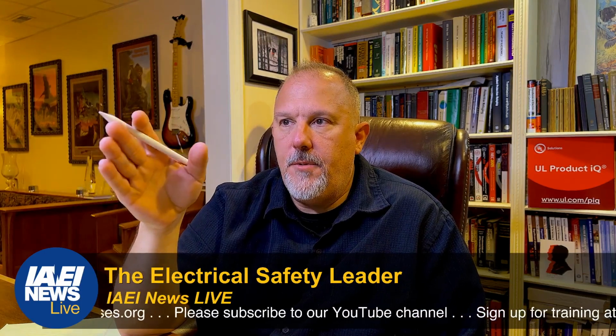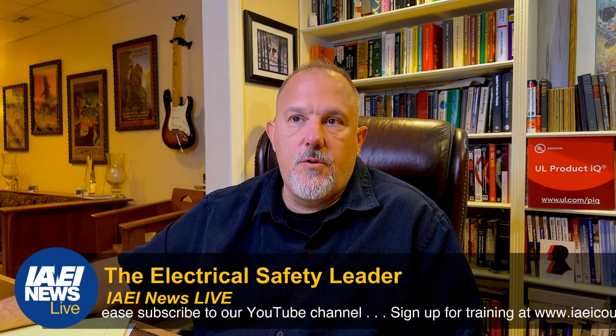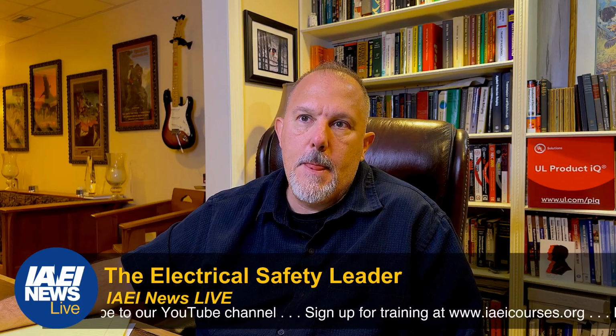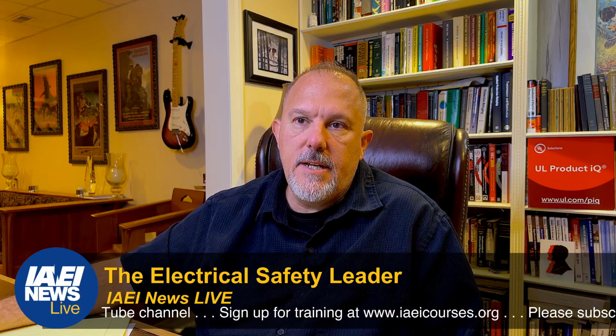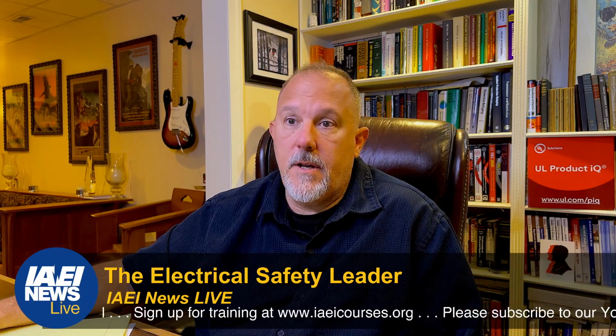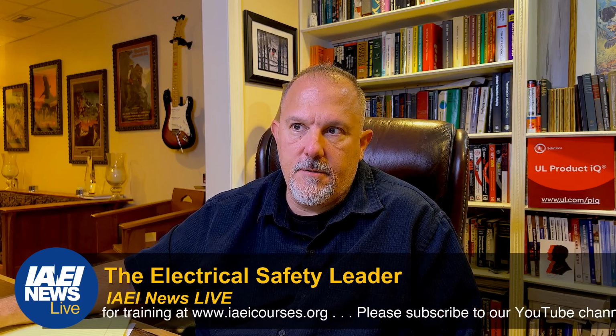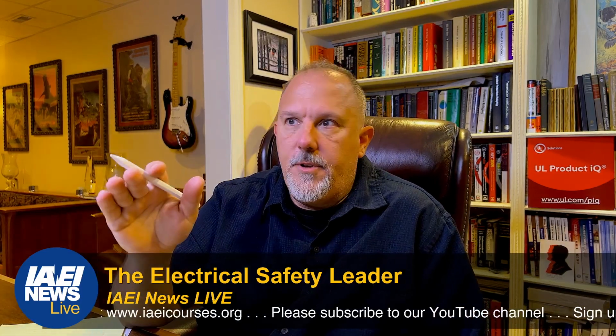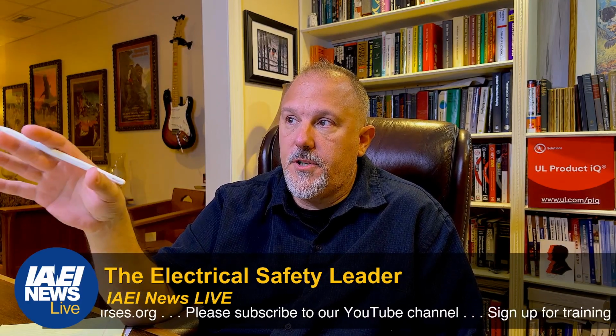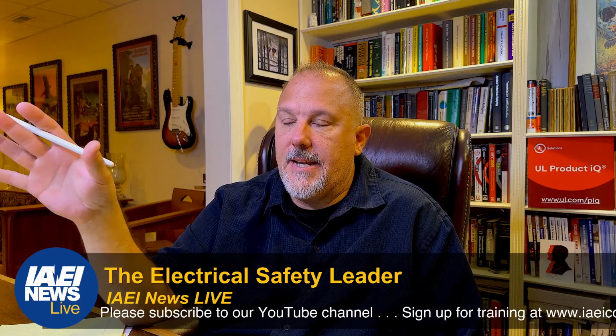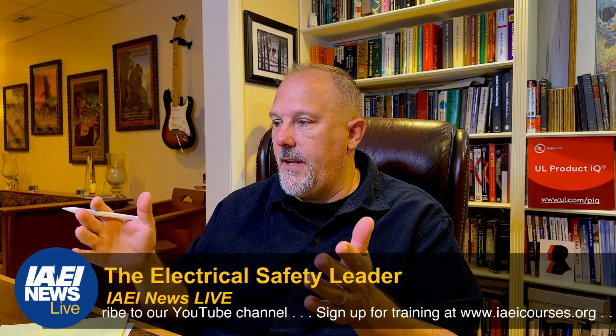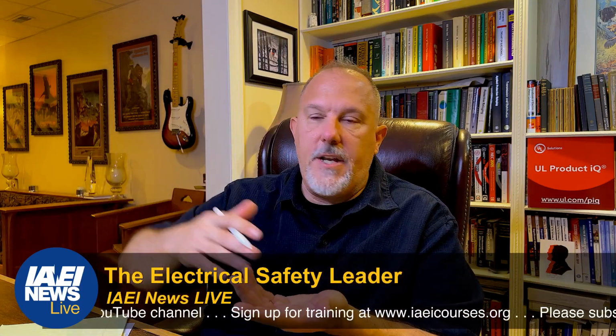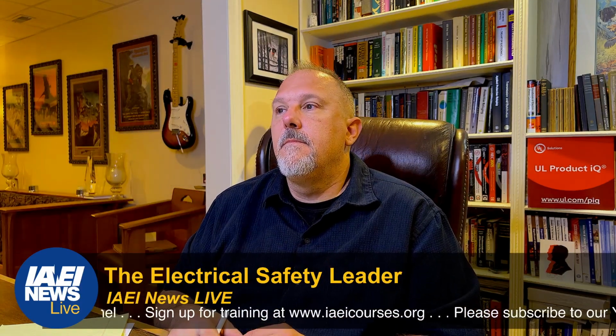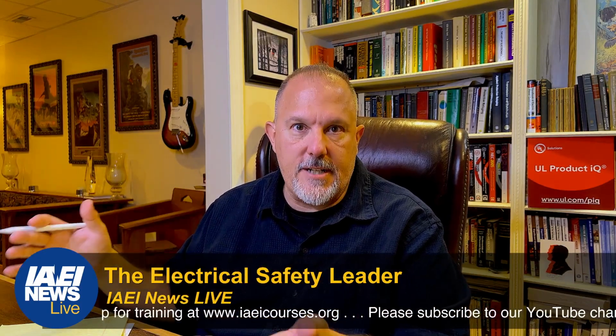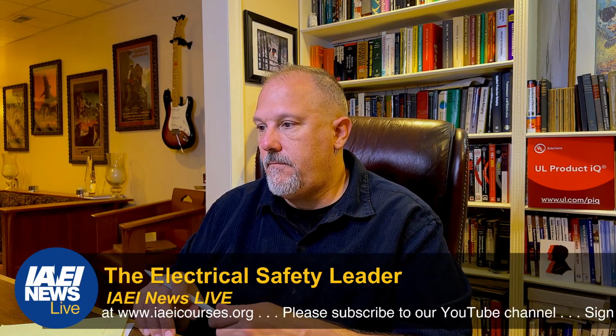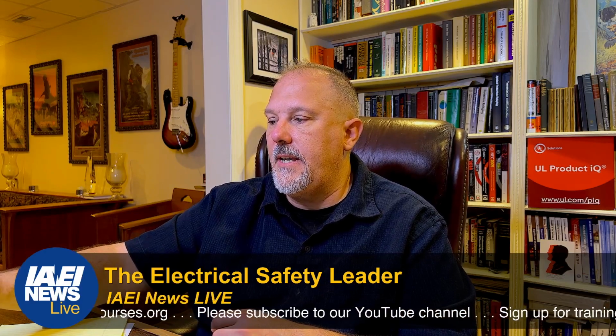Because remember, what do you need to meet from a dwelling unit perspective? A dwelling unit is a defined term, and it says that it's a single unit providing complete and independent living facilities for one or more persons, including permanent provisions for living, sleeping, cooking, and sanitation. So the thought process was, let's say I have a panel that's feeding a dwelling unit, and I take a feeder and feed another dwelling unit from that panel. That separate dwelling unit needs to have a surge protective device. So that was sort of the discussion. And what did we typically see?